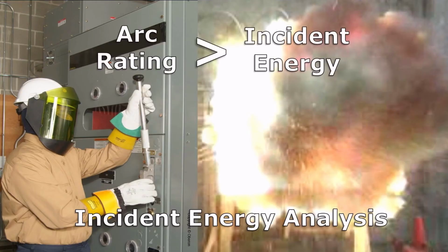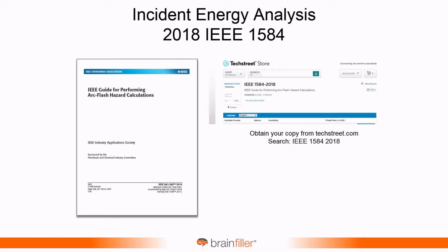I want to look at incident energy analysis next, because this is going to go into the next few subjects. So the concept of an incident energy analysis is, number one, you calculate or estimate the prospective incident energy, the severity of the arc flash. And then you select PPE and clothing with an arc rating sufficient for the incident energy. Simple enough. The incident energy analysis in most parts of the world, if this is performed, is based on IEEE 1584. The second edition of this standard came out in 2018.